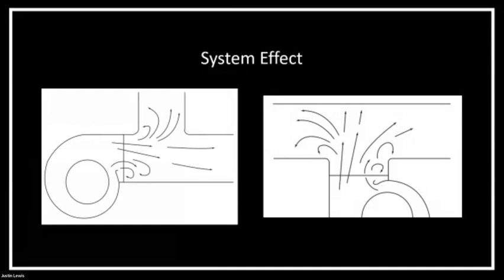Motors drive fans to produce work. That work is primarily expressed in two ways: pressure and velocity, or flow. System effect is a description of the inefficient transitions and causes of turbulence and pressure loss through a system that result in underperformance of airflow. Sometimes this is due to one or two issues that can easily be found, but more often we find that this is death of 1,000 cuts.